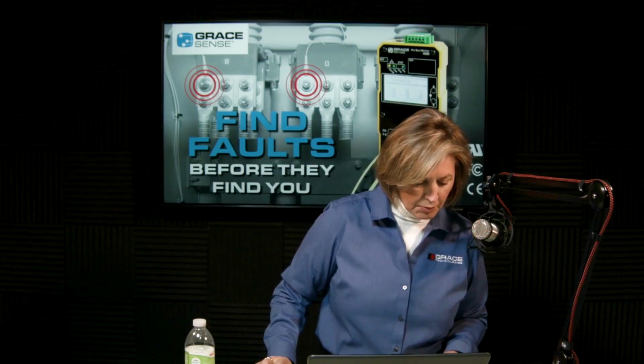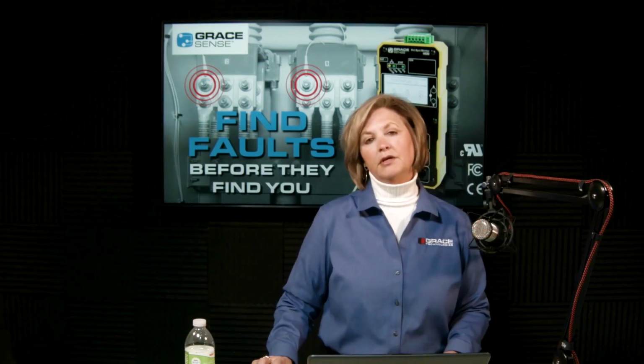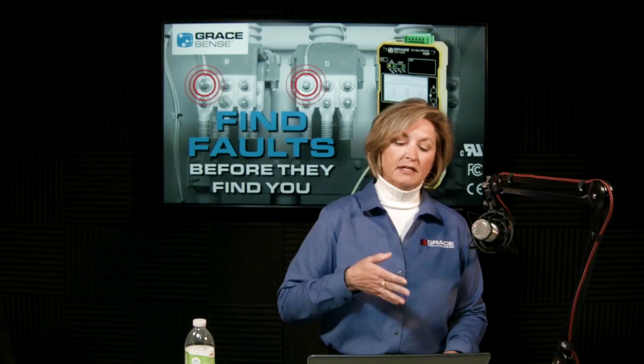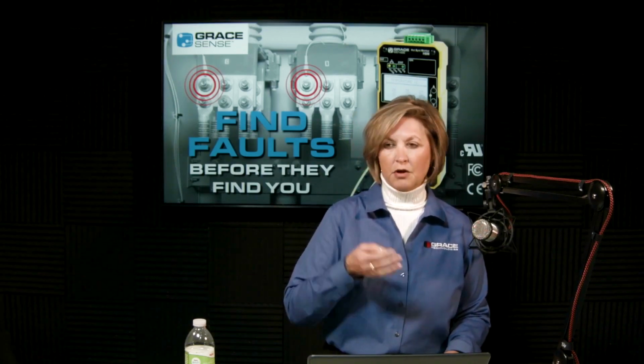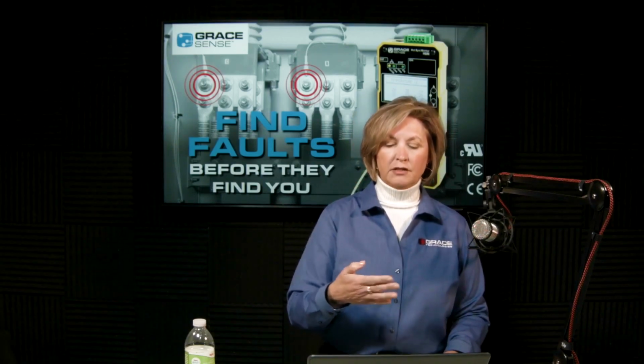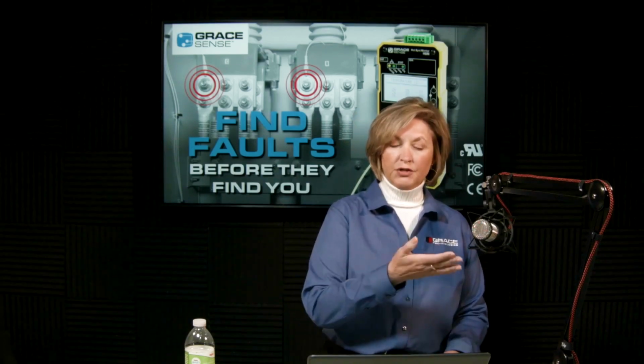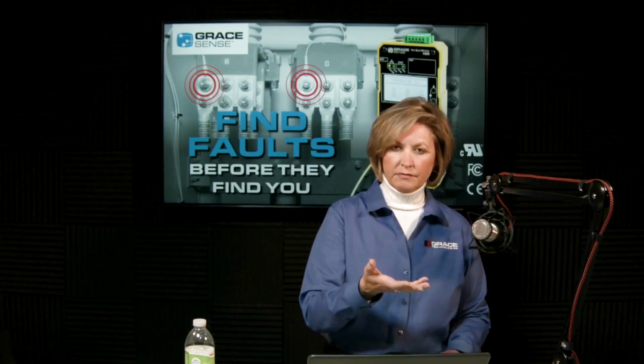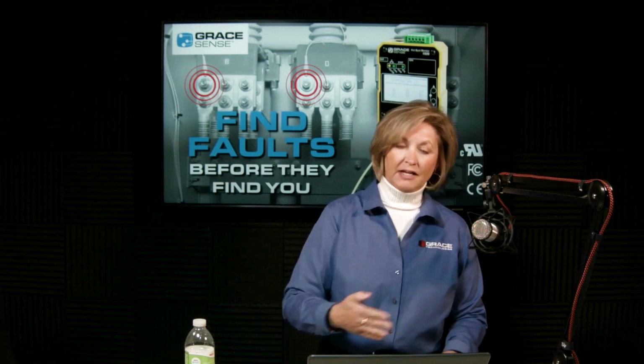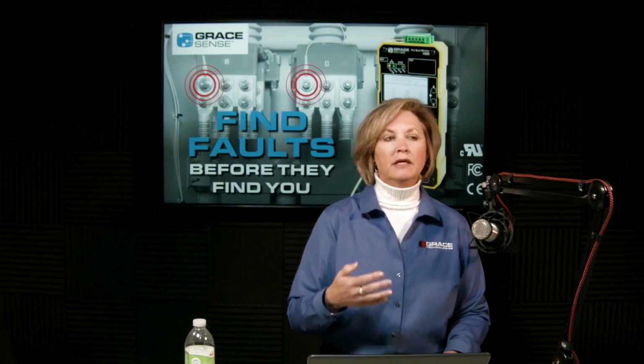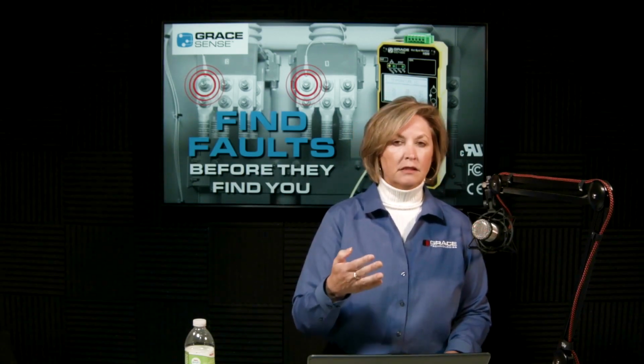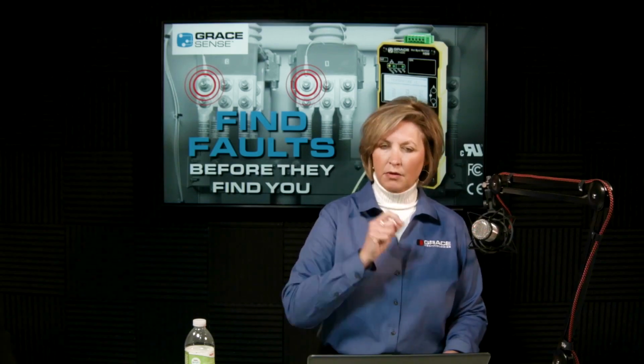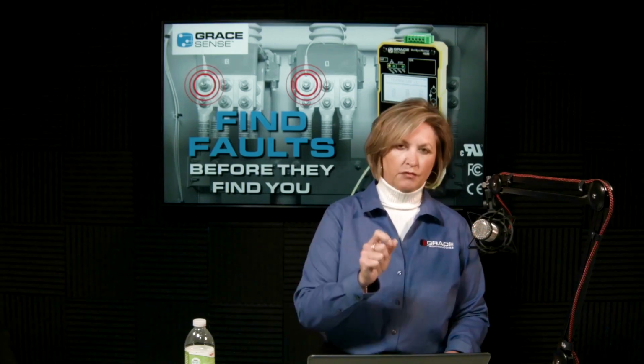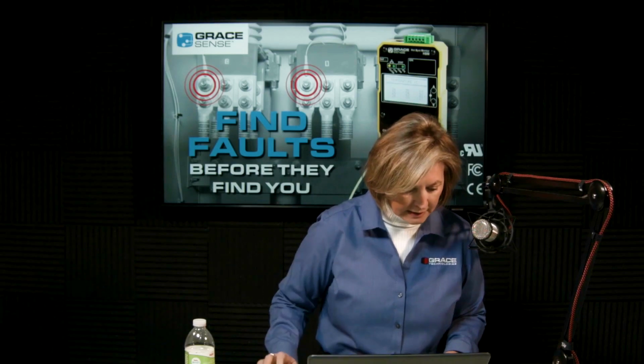The lug is not appropriate for transformers. Is there something else that can be used? So on the transformers, we always get it on the secondary side of the transformers. So at those bolted connection points that would go into the bus duct and into the distribution equipment, that's where we would get it. It is not rated to be in any hot oil or anything like that. So the secondary lug connections off the transformers is where we typically get that.